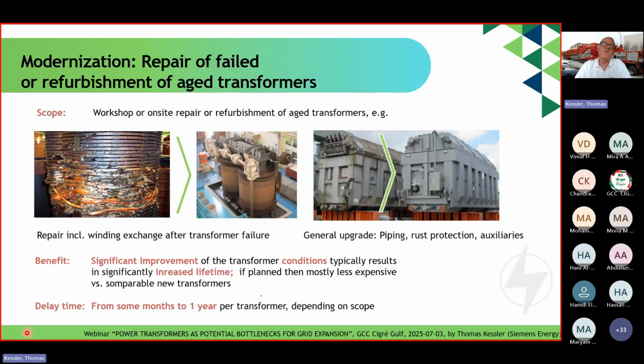Next step is repair of a failed transformer or refurbishment of an aged transformer. Remember the bathtub curve at the last third—this significantly improves the transformer conditions, either by replacement of a failed winding or windings, or by a general upgrade of the transformer including piping, rust protection, and auxiliaries. The benefit is significant improvement of the transformer conditions and, based on that, increased lifetime extension of the asset. The delay time for a transformer repair or refurbishment ranges from some months to 1 year, depending on the scope and the planning.